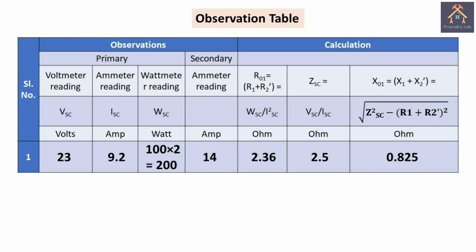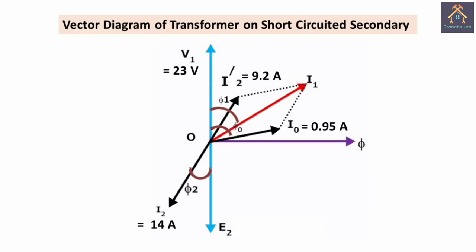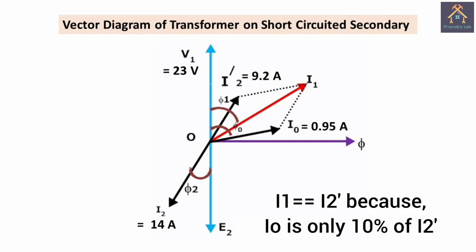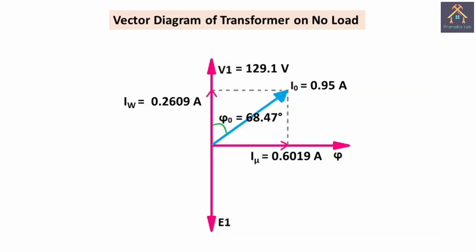This data is enough for drawing the vector diagram and the equivalent circuit of the transformer on short circuit test condition. In the vector diagram, the no-load primary current is 0.95 ampere, measured from the open circuit test. The primary load current I2' is 9.2 ampere, and the secondary current I2 is 14 ampere. I2' and I2 are in antiphase with each other. The resultant of the no-load current I0 and load current I2' is the primary current I1. I1 and I2' will be nearly the same because the no-load primary current is negligibly small. From the open circuit test vector diagram, the no-load current had two components only — Imu and Iw — and there was no load current component; the no-load primary current was the only primary current taken by the transformer.